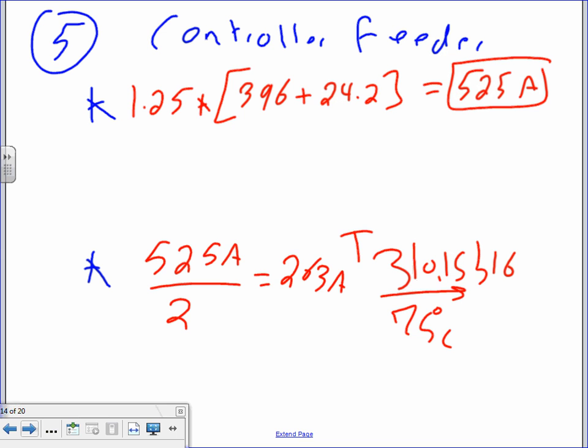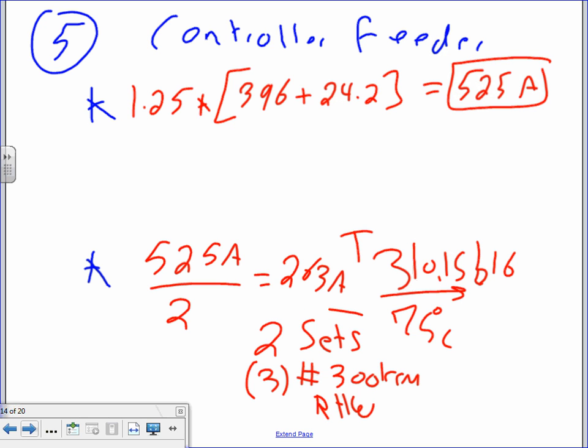Take it to 310.15(B)(16) under, this is, believe it or not, B, under the 75-degree column. Gentlemen, you get 2 sets of 3 conductors. Each one of them is number 300 kcmil RHW. That's it. Any comments, guys? Any questions? Any comments? Any questions? Does it make sense? So that would be the feeder coming from the controller. Okay. Comments, guys? We've done that before, right? 5. Straightforward, not a whole lot of gimmick. You parallel them. Every time you hit more than 400 there, you have to parallel. 400 is your cutoff. Okay?